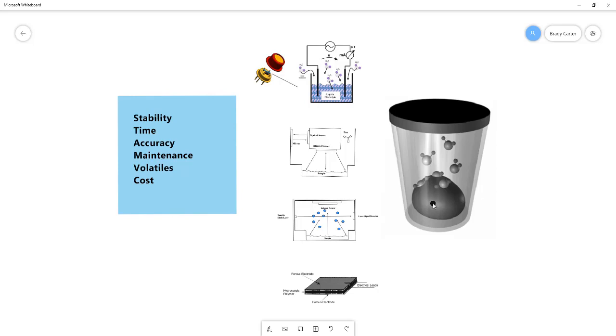The requirements that are set to indicate that equilibrium has occurred can also vary. And so this means the only way to track equilibrium is to know that you're at a static state, so there aren't any changes over time. And so what's used is a setting that looks at water activity values over time, and when the variation drops to a certain preset level, that indicates the end of the test. And so the more stringent you set that, the more likely you are to have equilibrium, but it also extends the test time. And so if there are differences between those settings, it will result in differences in analysis times.